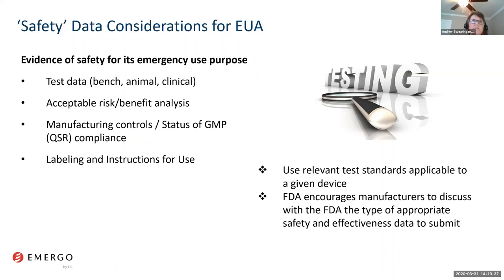Also, safety data needs to be provided. Again, test data is important. A risk-benefit analysis that shows that the risks are not too severe and that the benefits outweigh any potential risks, a summary of the manufacturing controls that are in place, and labeling and instructions for use that are needed in order to use the device safely. I do want to point out and emphasize that complying with relevant standards automatically infers a certain level of safety and effectiveness for the device. And if there's any doubt as to what type of testing to perform on your device, the FDA encourages the manufacturers to engage in a discussion with them on that. Next, please.